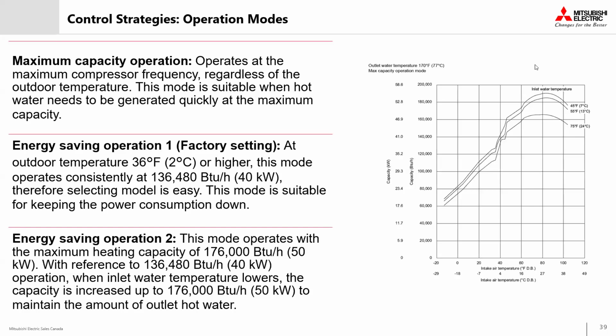So first one we see here is our maximum capacity mode. This setting runs the compressor at full output, which is ideal when there's a sudden spike in hot water demand, and you'll need that rapid tank recovery. Think early morning in a hotel or a gym just after rush hour when we have the most consumption.